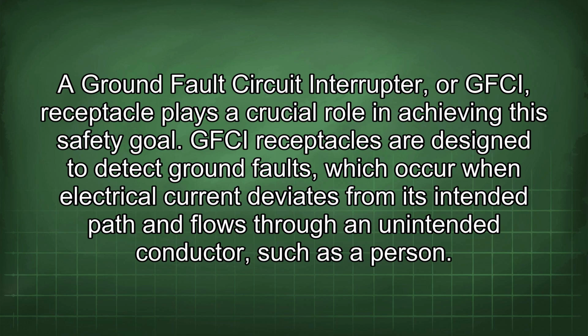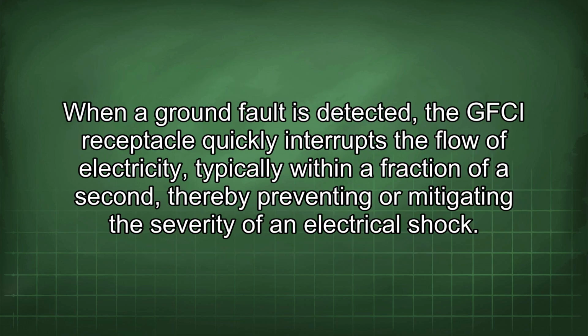GFCI receptacles are designed to detect ground faults, which occur when electrical current deviates from its intended path and flows through an unintended conductor, such as a person. When a ground fault is detected, the GFCI receptacle quickly interrupts the flow of electricity, typically within a fraction of a second, thereby preventing or mitigating the severity of an electrical shock.